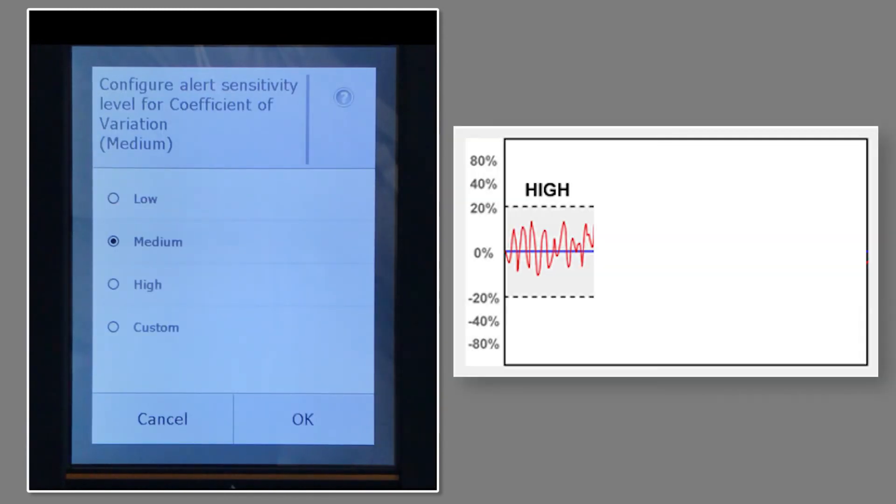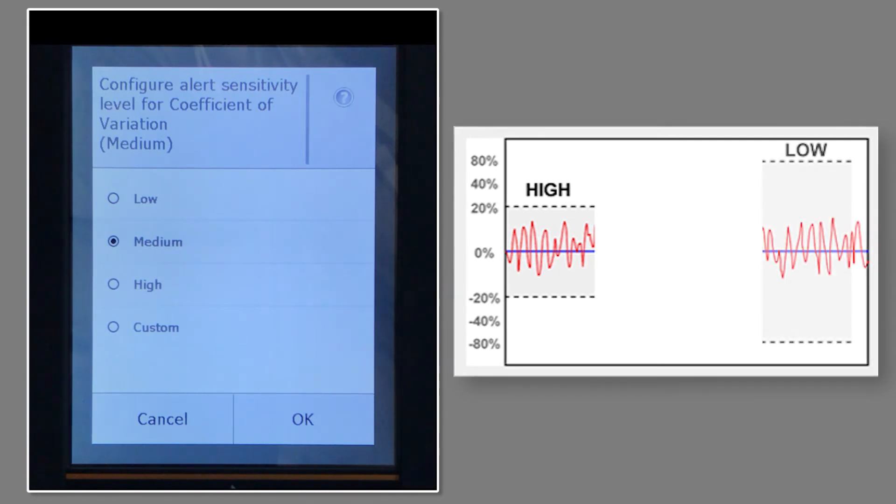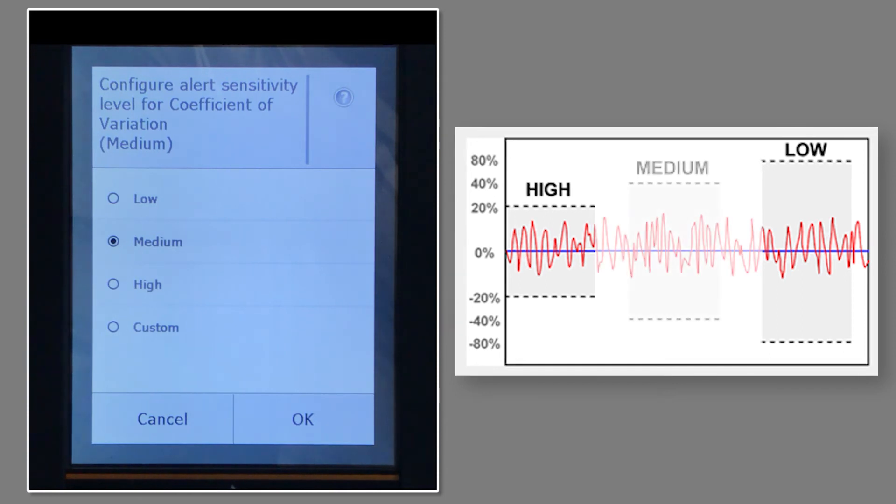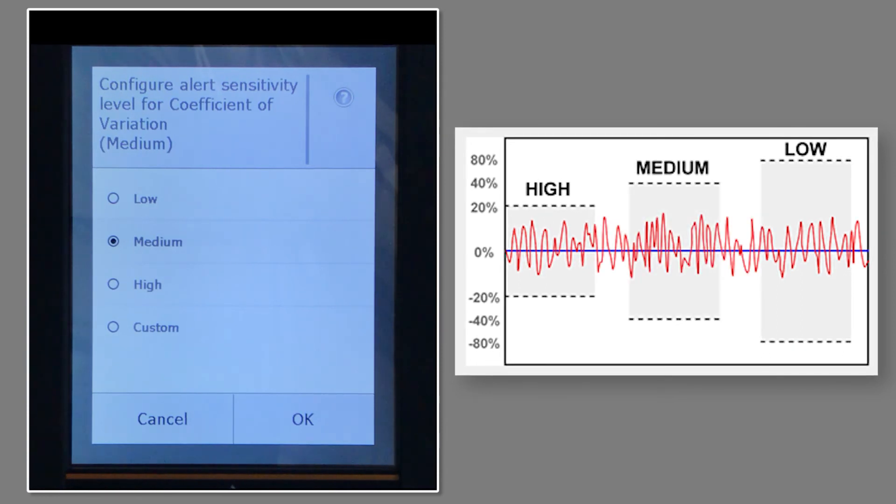Now we select the sensitivity threshold with high being the most sensitive to changes in the process and low being the least. You can use trends from a data historian to determine which level is best for your process or use the default setting of medium, which I will be doing.